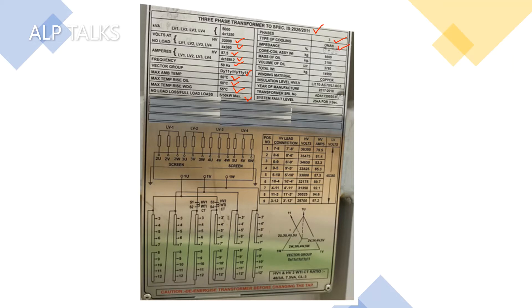Cooling: most 90% of transformers will be ONAN. Some people may ask for ONAF, but that is very rare. Impedance is punched on the transformer after testing; here the value is 6.36%. Core and coil assembly weight is 6600 kg. Mass of oil is 3100 kg, and volume of oil is 3790 liters. Generally the density of oil is around 0.82815, but as per IS, 0.89 is the density. This is a 14 ton transformer.